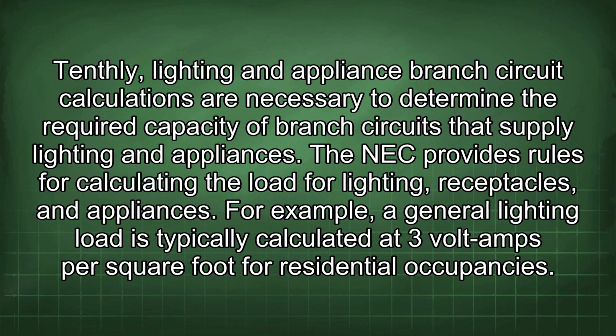Tenthly, lighting and appliance branch circuit calculations are necessary to determine the required capacity of branch circuits that supply lighting and appliances. The NEC provides rules for calculating the load for lighting, receptacles, and appliances. For example, a general lighting load is typically calculated at 3 volt-amps per square foot for residential occupancies.